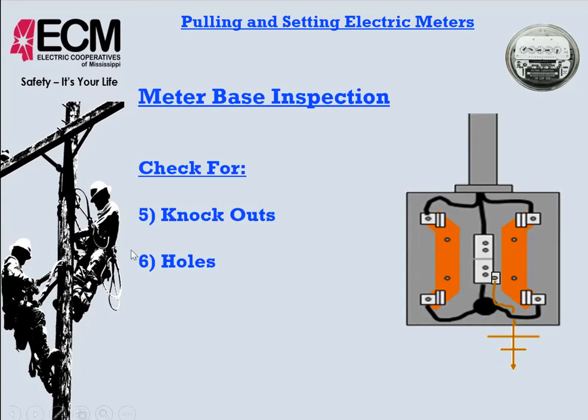Still checking the meter base up. One of the things we need to pay attention to prior to setting a meter is the knockouts in the meter base, making sure that there are no holes in the meter base anywhere. That allows people to access there, kids stick things in there, potentially become electrocuted, and it also allows wasps and different insects and varmints to get in there as well. Make sure there aren't any holes and those knockouts have not been knocked out.